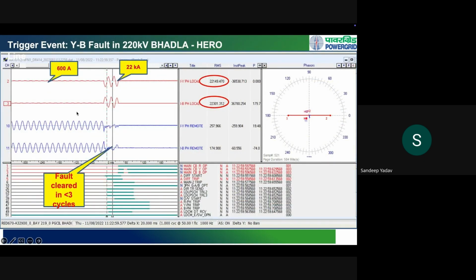So this is the snapshot of one of the disturbance records. If you take a look, this is a Y to B fault, a yellow phase to blue phase, phase to phase fault. The total fault current fed from the grid side is 22 kiloampere, or 22,000 ampere. So 22 kiloampere fault current is fed from the grid side.